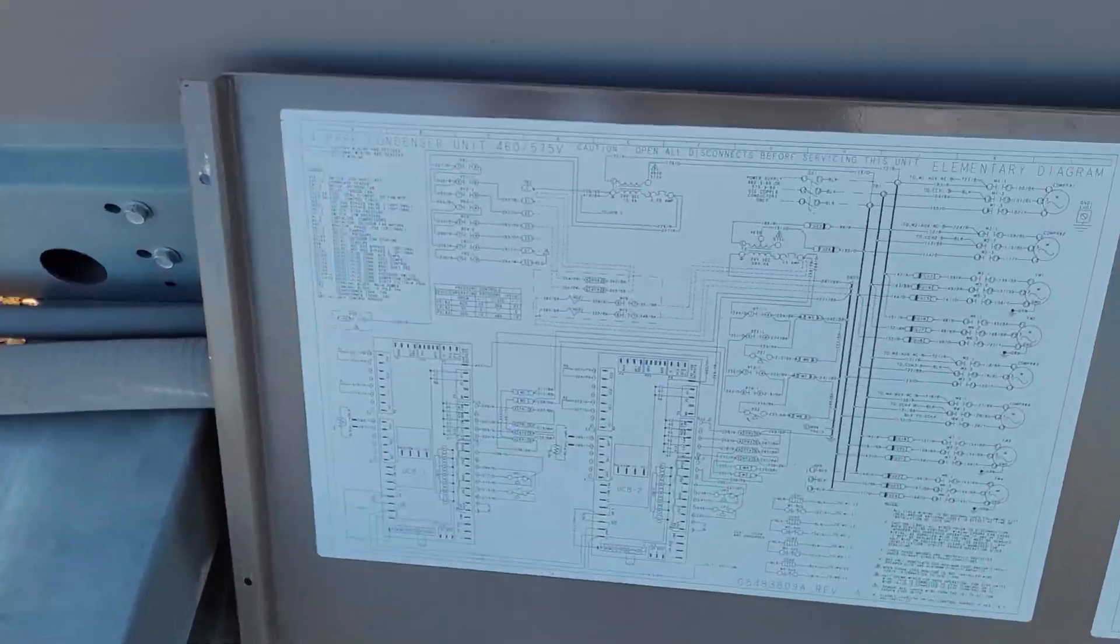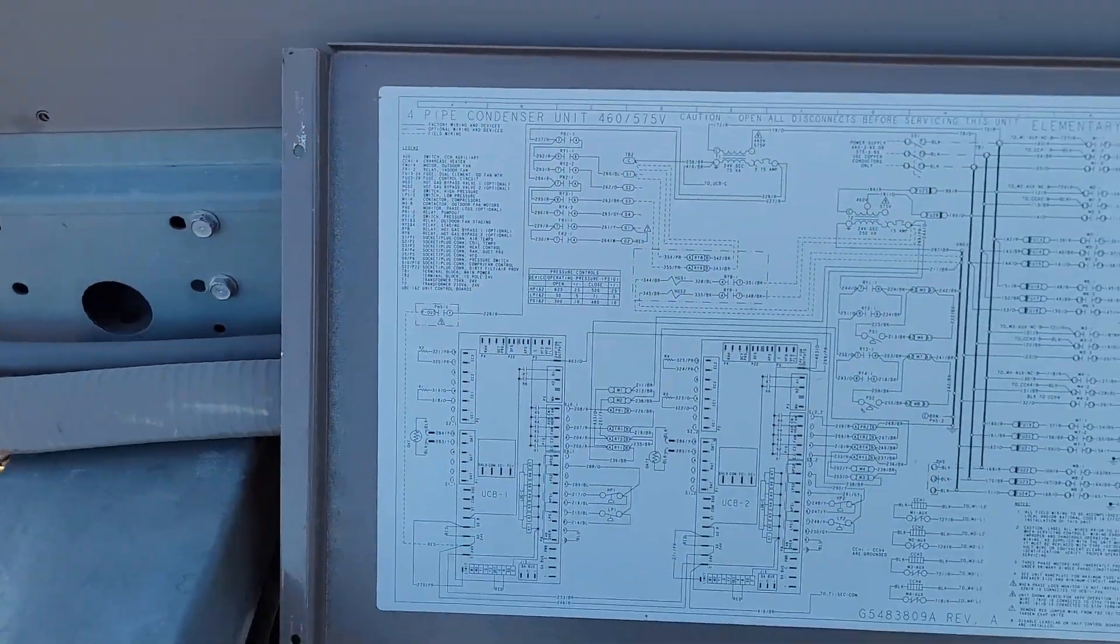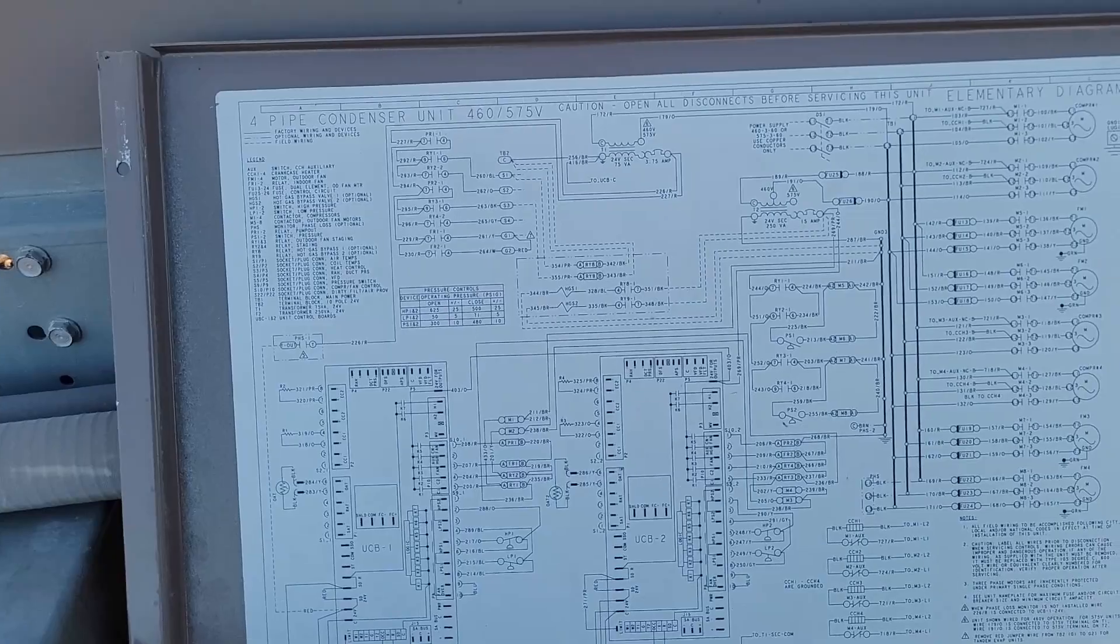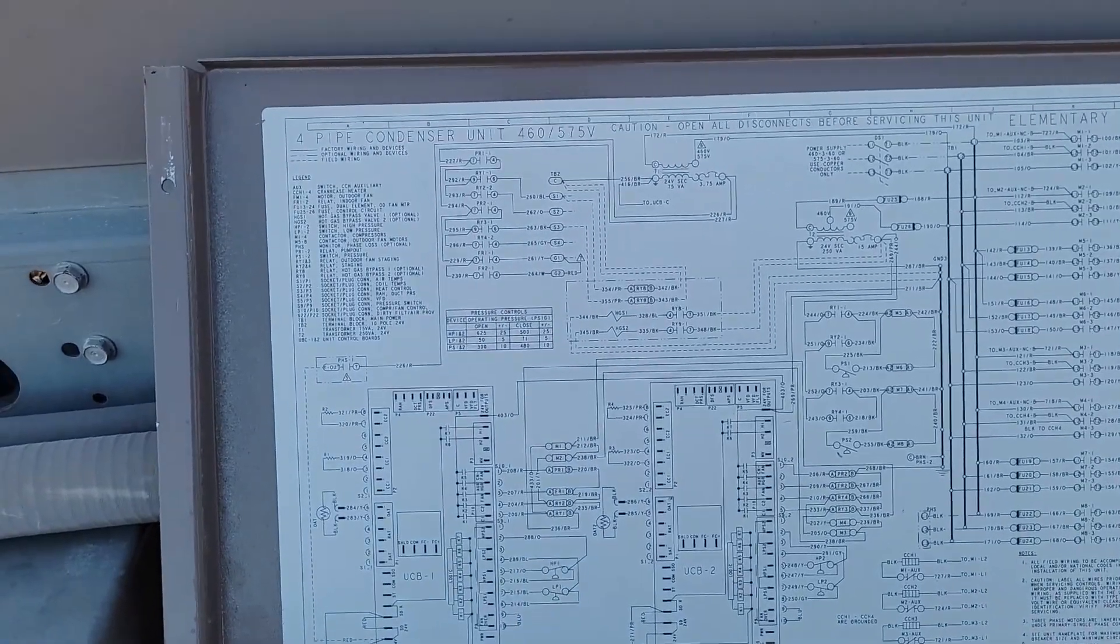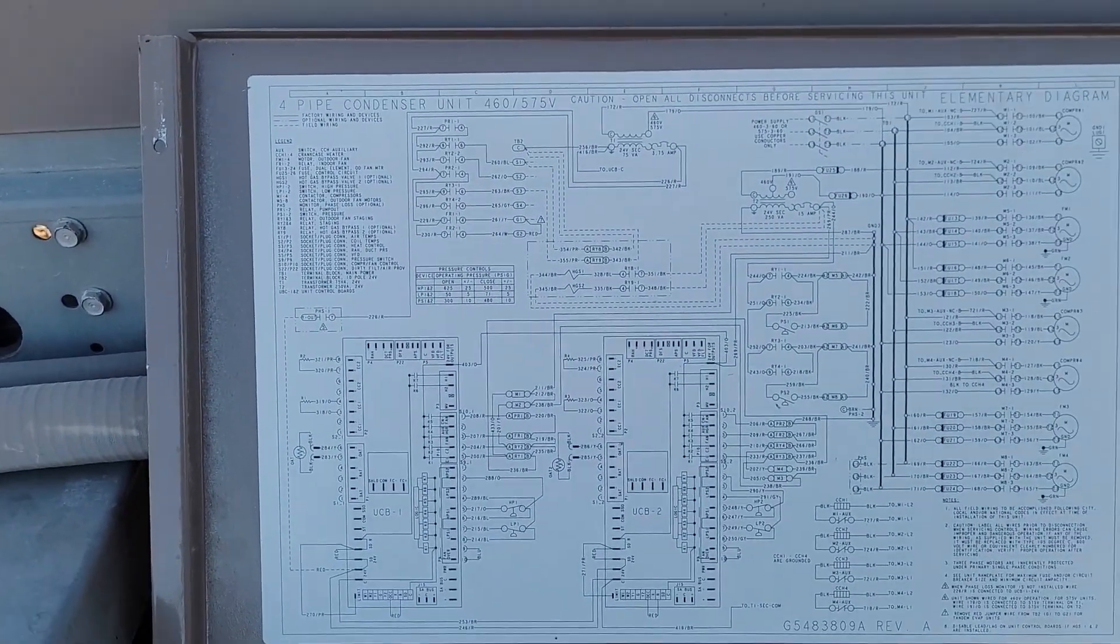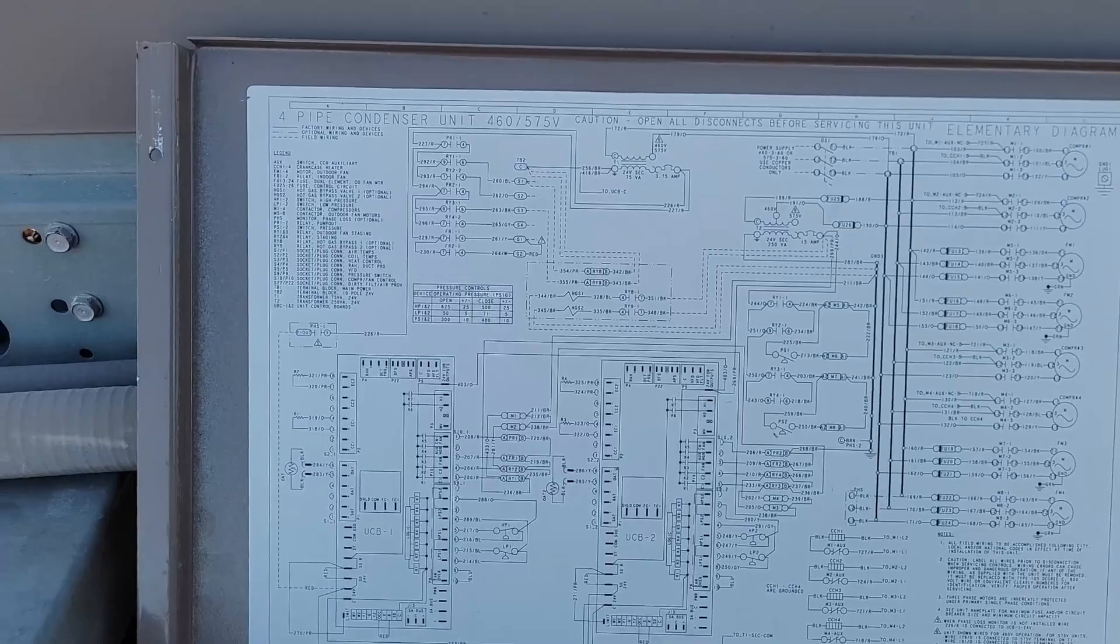So then I'm looking at this diagram, and I figured out, my controller stops calling for cooling, but the cooling still runs. And I notice I've got 24 volts coming from somewhere, so I start digging into it and trying to figure out where it's coming from.